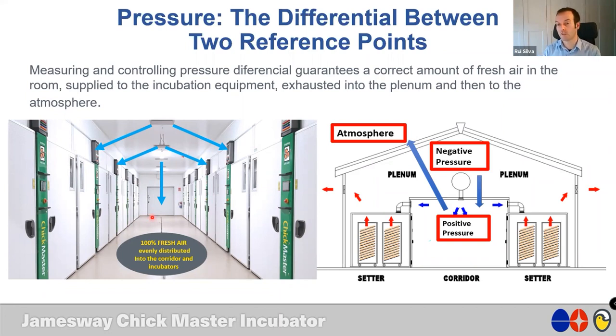Because sometimes people just care about, okay, I need that much CFM in my room. Okay, but do you have it with quality? Do you have a short stratification of temperature between the top and the bottom, and it's not direct to the machine? Because your machines radiate. So when you are putting it this way, you are already treating part of the radiant heating coming from your machines. Therefore, if your set point is at 25, what you need to do is supply at 23, because the 2 degrees difference will come from radiant heating from the fascia of the machine.